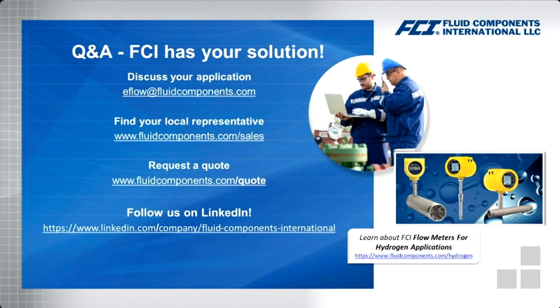Are all thermal manufacturers able to calibrate meters in hydrogen gas? Boy, great question. I can only speak to the capabilities of FCI, but we do have a state-of-the-art Cal Lab in our facility, and we are able to calibrate those meters in hydrogen gas at your process conditions. So that would be a question directed to the individual manufacturers. Some of them have those capabilities, some of them outsource those capabilities, and some simply use an air equivalency calibration. My recommendation, right, ask those questions and get those answers from those manufacturers.